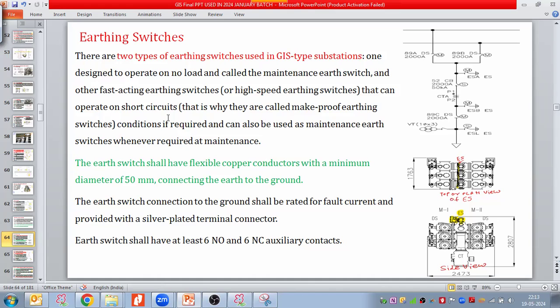Short circuit conditions, if required, and can also be used as a maintenance earthing switch whenever required at maintenance. So if you see this, I have taken one extract of the GIS SLD. In that, if you see the disconnectors here, we have a separate model for the earthing switch. But this earthing switch must have the insulating link here, right?